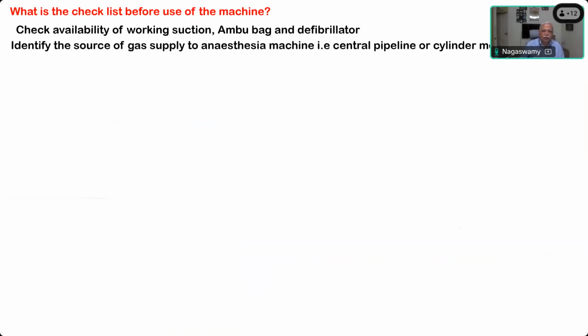Identify the source of gas supply to the anesthesia machine, whether it is central pipeline supply or a cylinder supply. Then what is the next step? Supposing it is a central pipeline supply, as it is very common in all the major hospitals nowadays. What is the next? Connection, sir. We have to connect the pipe. Check the touch test to see the connection. But more than that, what important safety precaution you have to do? To check the pressure. That will be displayed in the machine itself. You don't have to worry about it, because pipeline pressures and cylinder pressures are displayed in all the modern workstations. So you will know what the pipeline pressure is. They give you a constant of 45 to 55, isn't it? Yes, sir. But if it is a central pipeline supply, what is the most important safety check you should do?